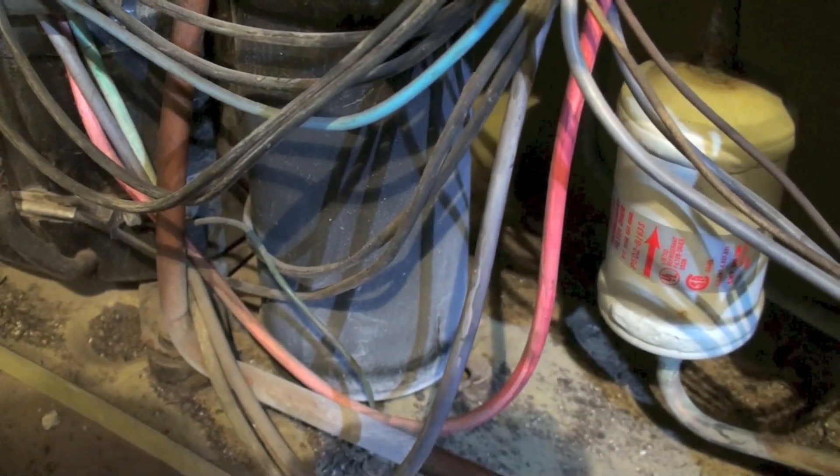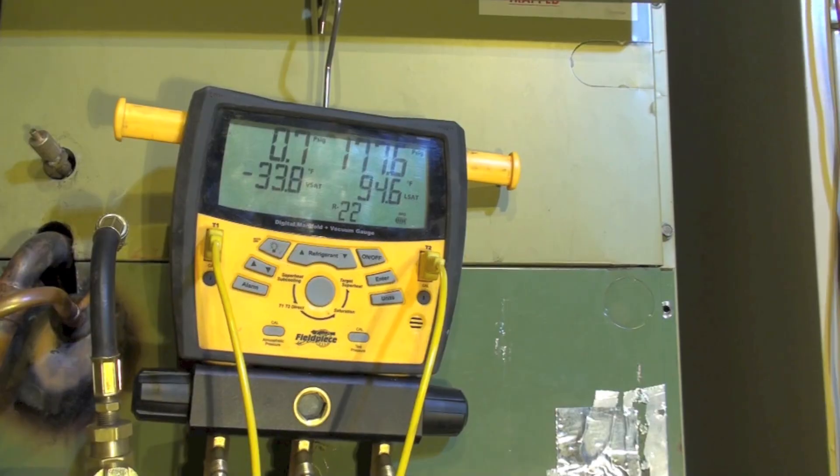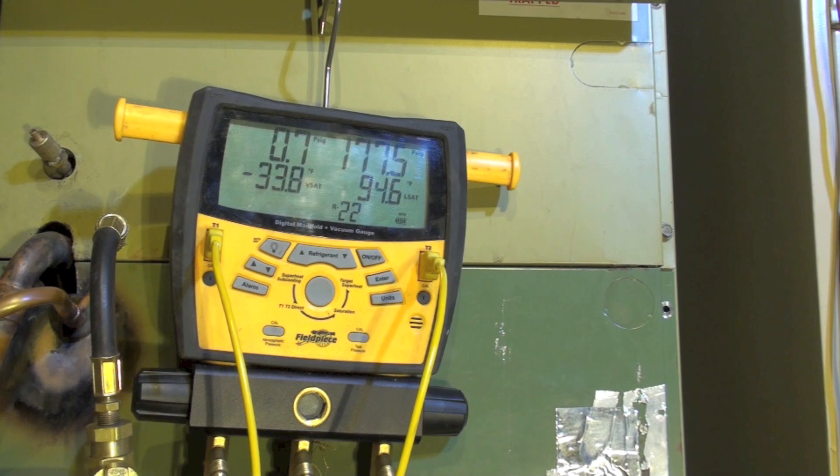Okay, this is about the lowest I could get. I think it's pulling some refrigerant out of oil that's in the accumulator and I don't want to give it any more time. I'm going to go ahead and shut it off. It should equalize quickly if we have a valve problem.